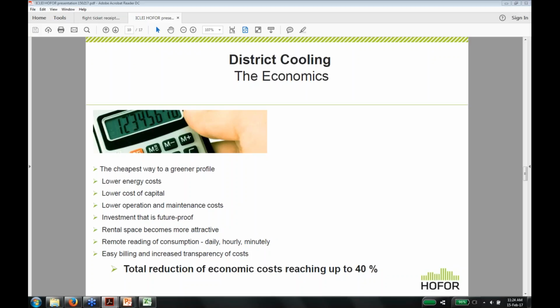On the other hand, we remote-read the consumption all day, hourly, so we can always advise our customers how to optimize their system, because we have an agreement that we deliver cold water at 6 degrees and they heat it up to 16 degrees. That means they should always have a delta T of 10. We remote-read and monitor this so we can always recommend how to optimize his system.